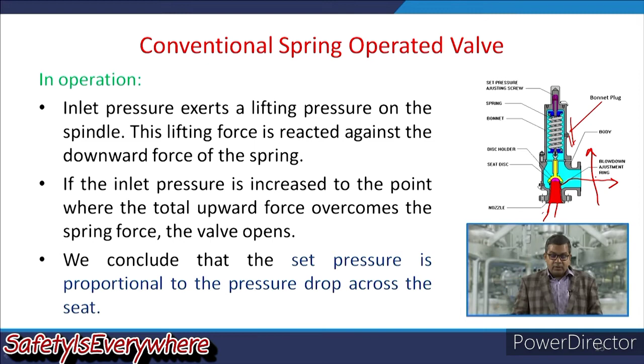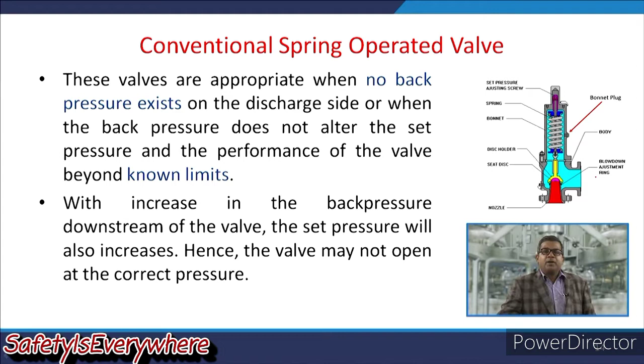These valves are appropriate when no back pressure exists on the discharge side, or when the back pressure does not alter the set pressure and the performance of the valve beyond the limit. With an increase in the back pressure downstream of the valve, the set pressure will also increase, hence the valve may not open at the correct pressure. Additionally, the discharge is proportional to the pressure difference across the seat, so an increase in the back pressure hinders the flow through the valve. Practically, they can be used without any problem in case of atmospheric discharge.